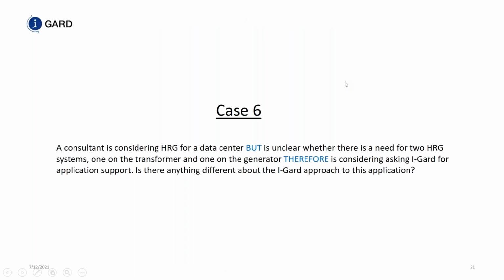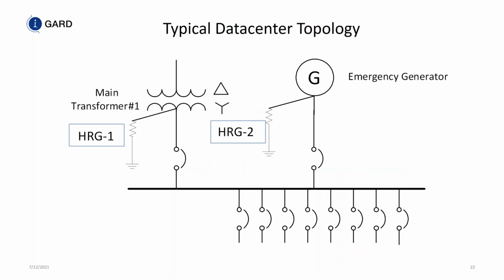Case number 6, a consultant is considering high resistance grounding for a data center, but is unclear whether there is a need for 2 high resistance grounding systems, one on the transformer, one on the generator. Therefore, is considering asking iGard for actual application support. This actually happened, and we have supplied 2 high resistance grounding systems because the topology of a data center is to have a transformer and a generator as sources, and then they share the bus. So basically, there's no tiebreaker in between here.